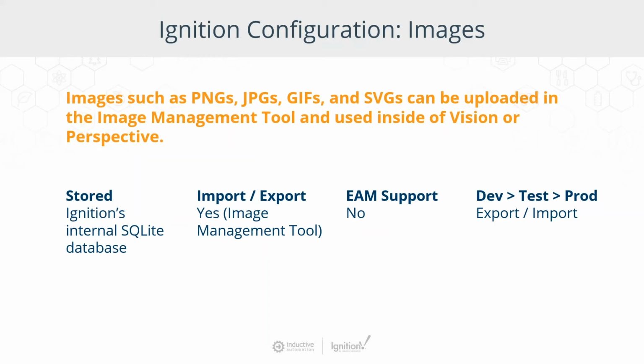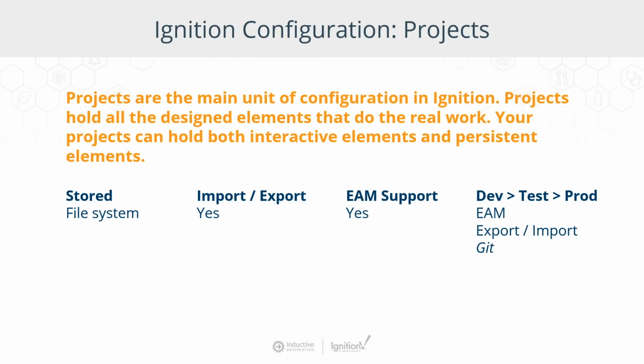One quick thing to add to that, if you've never done anything with specific images: if all you've done inside Ignition is use Symbol Factory, that doesn't qualify for what we're talking about here. I've talked to a growing number of folks who ask, what is image management? There's a separate section inside Ignition that allows you to upload images, under Tools, Image Management. If you've never used it before, you'll never need to synchronize images. If you're just using things from Symbol Factory, those end up inside the projects, which we're going to talk about now.